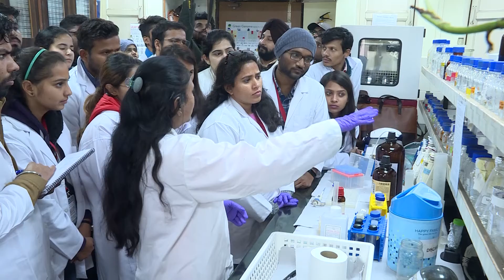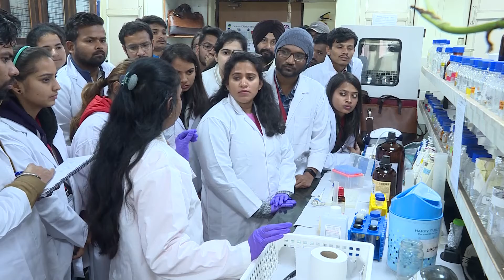In the UPLC, one advantage is that you only need 4 to 5 microliters of your injection. Otherwise in HPLC, where the column is 5 micron, you need 20 microliters of your injection. In this, the particle size of the column is very small, 2.1 micron as compared to 5 micron in the HPLC. If the column has a 2.1 micron particle size, then you will have good resolution, which means the peaks in the UPLC will be high resolution. Peaks you can see easily, sharp fine peaks will be there. So different dilutions you have to make for the standard.